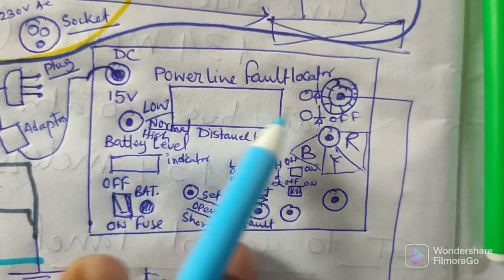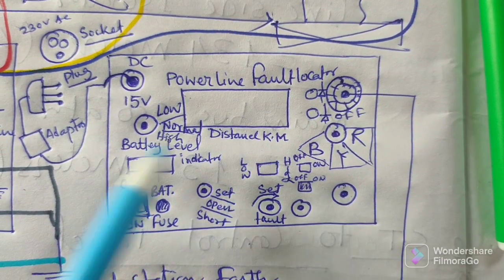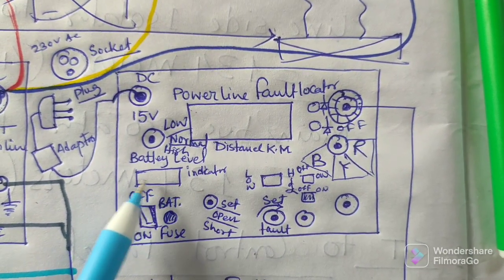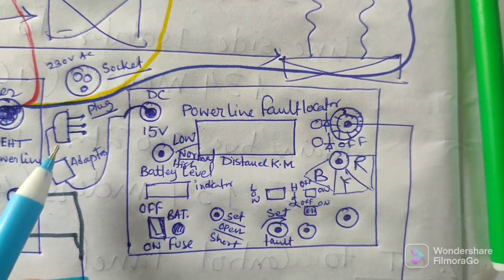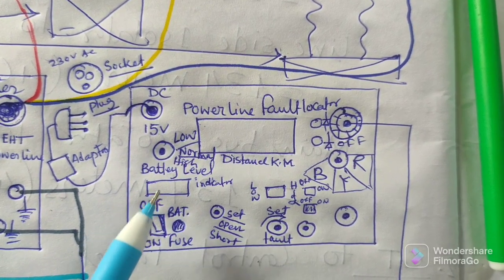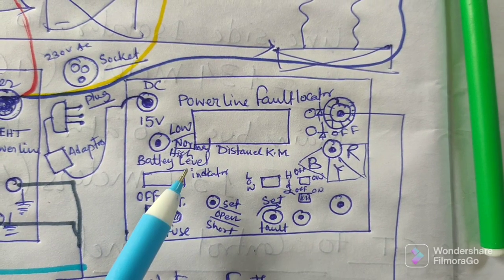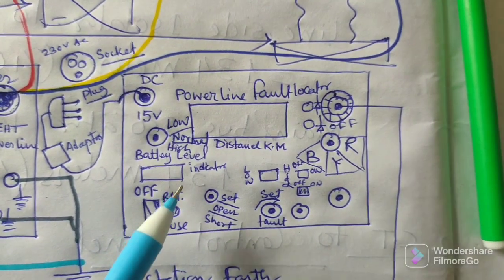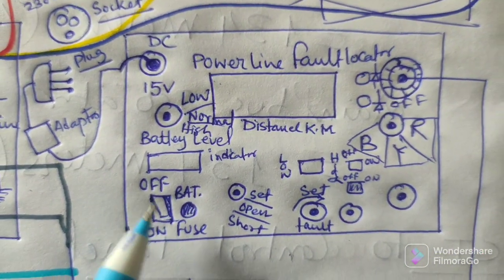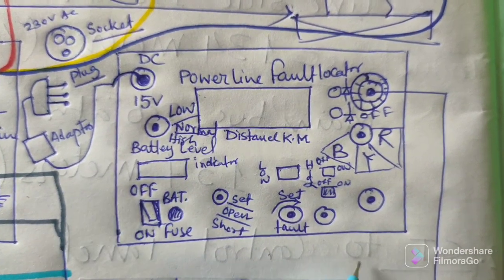This is the display where you will get information about where the exact fault has occurred — it gives the distance in kilometers. This is the 15-volt charger socket and the battery indicator showing the condition of the internal battery. If the battery condition is poor, plug in the socket for direct power. If the battery voltage is 13 or 14 volts DC, the machine will function properly. Before testing, ensure the battery condition is good because a good battery is required for accurate fault location. This is the on/off switch, and after switching on, one light blinks to confirm the machine is on.